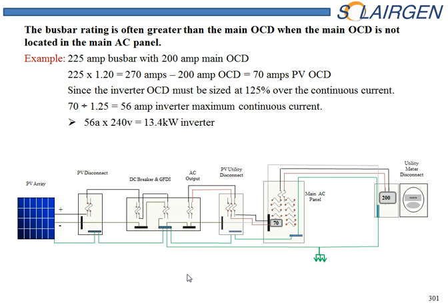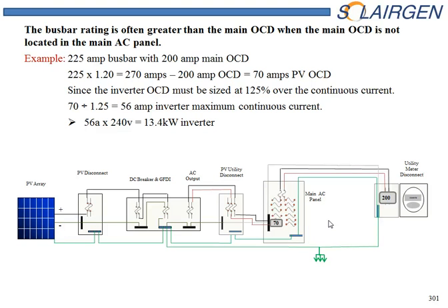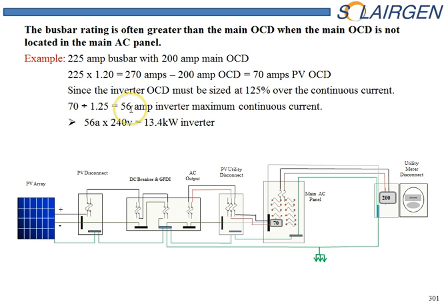Option two is the same option but with a different situation. In this case, we have the overcurrent device outside at the meter base. The main loads panel bus bar does not have an overcurrent device in it. Often when you buy this panel separately without an overcurrent device, the ampacity is greater than 200 amps. In this example, we're using a typical load center rated at 225 amps. 225 amps times 120% gives us 270 amps. Subtract the 200 amps as we did before, and this leaves 70 amps — giving us a much higher capacity for our inverter. So we have a 70 amp overcurrent device, and again we divide by 125% to find the continuous current of the inverter, giving us a much larger inverter input capacity.